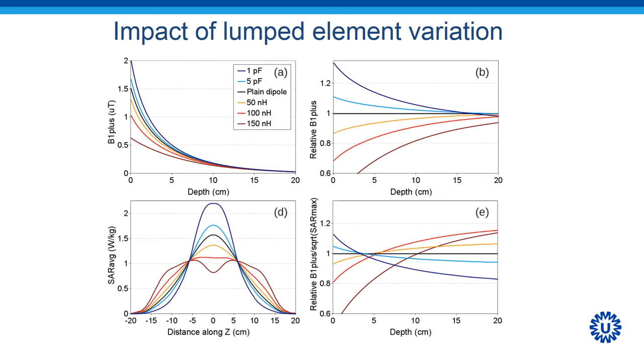The second diagram, where everything is plotted relative to the plain dipole, shows that this effect is actually most pronounced at the surface and decays at larger depths. If we look at the SAR distribution, we can also see that capacitors enhance the SAR levels, while inductors reduce the SAR levels.